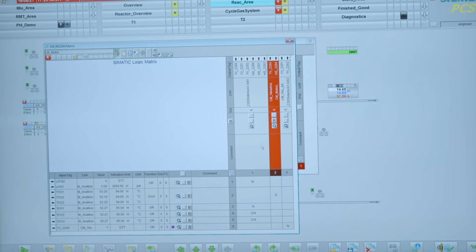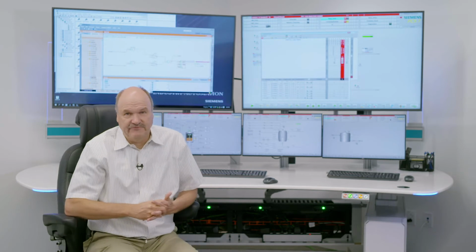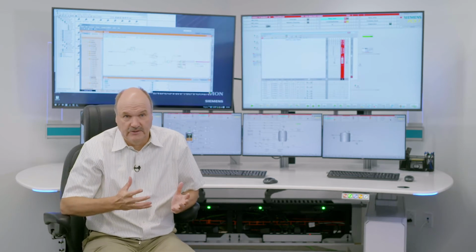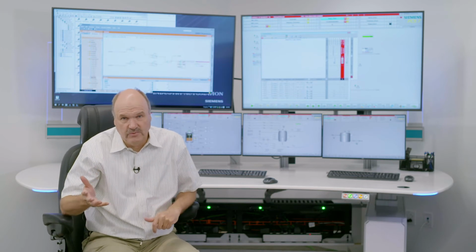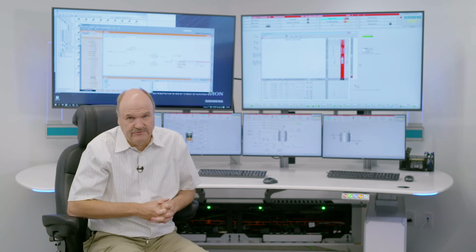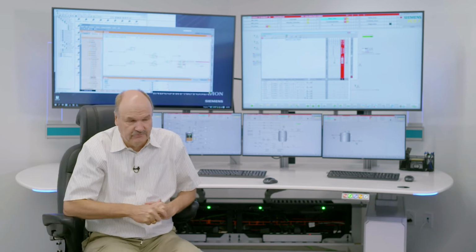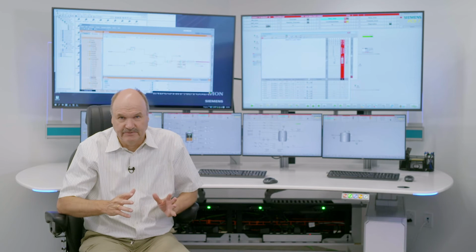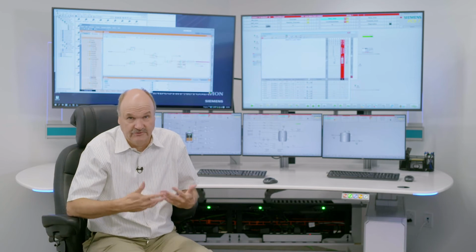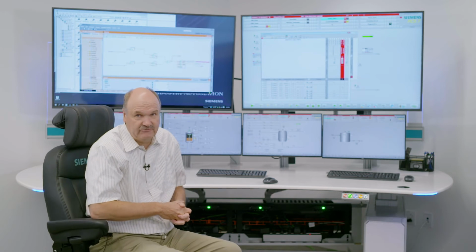the system automatically. In between a cause and effect is a so-called intersection logic equation, which decides if this happens, should we latch the effect and call the operator to take a corrective action? Or do we only need to momentarily close something or vent something and then go back in the normal process? Now, what we have done in PCS7 is we brought this whole set of detection of causes, showing what the effects are, and the user interface to all of those to the HMI screen out of the box. So you configure it once in one comprehensive place, and then out of the box, the whole visualization unfolds in front of the operator without any extra effort.